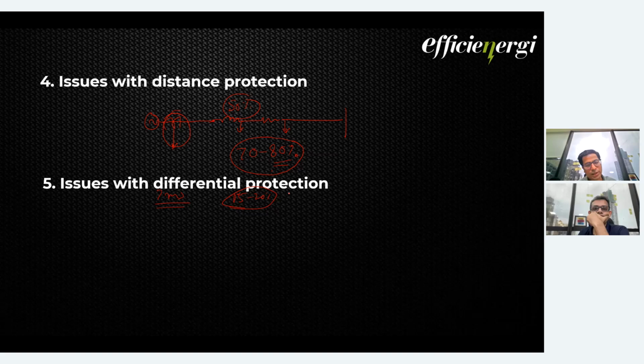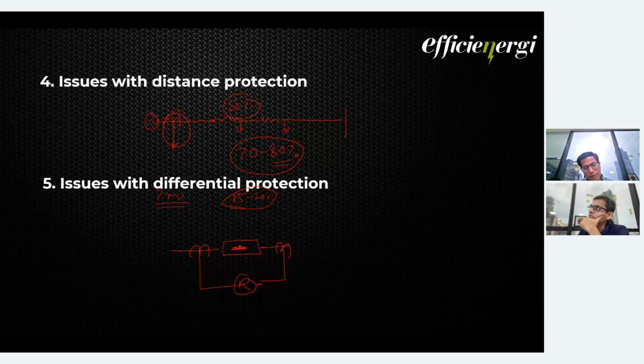Then there are issues with differential protections. Now, you know what differential protection is. This is your equipment unit protection, and you have different CTs. With a normal differential protection, this is a problem. If there is an external fault, differential protection must obey that for an external fault it should not operate. But what happens if there is a heavy fault external to the zone, and if this CT or this CT gets saturated? Then this acts as a differential protection, because this CT will read, let's say, 10 ampere, and this CT will read, let's say, 8 ampere. So the difference is 2 ampere, and this 2 ampere will be acted upon, and this differential relay will operate because this CT is getting saturated.